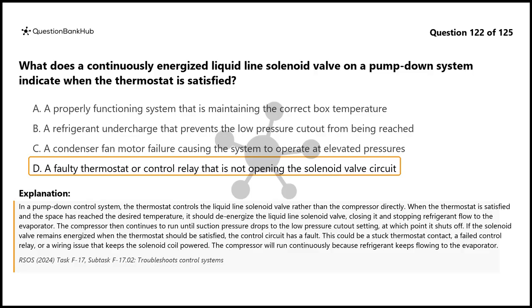The compressor then continues to run until suction pressure drops to the low-pressure cutout setting, at which point it shuts off. If the solenoid valve remains energized when the thermostat should be satisfied, the control circuit has a fault. This could be a stuck thermostat contact, a failed control relay, or a wiring issue that keeps the solenoid coil powered. The compressor will run continuously because refrigerant keeps flowing to the evaporator.